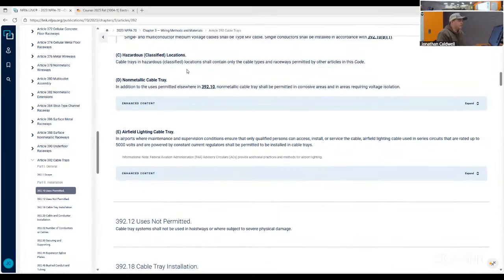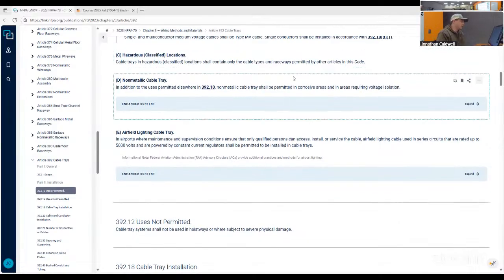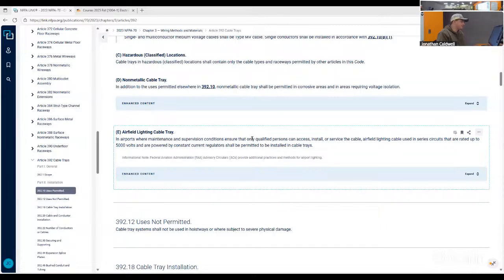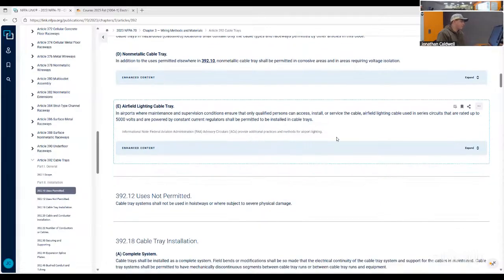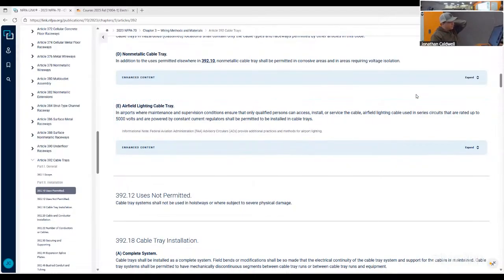That being said, the tray itself doesn't care. It is literally the cables or conductors you're running in that tray. That's when you have to care about the hazardous location. Airfield lighting cable tray. In airports where maintenance and supervision conditions ensure that only qualified persons can access, install, or service the cable, airfield lighting cable used in series circuits that are rated up to 5,000 volts and are powered by constant current regulators shall be permitted to be installed in cable trays.